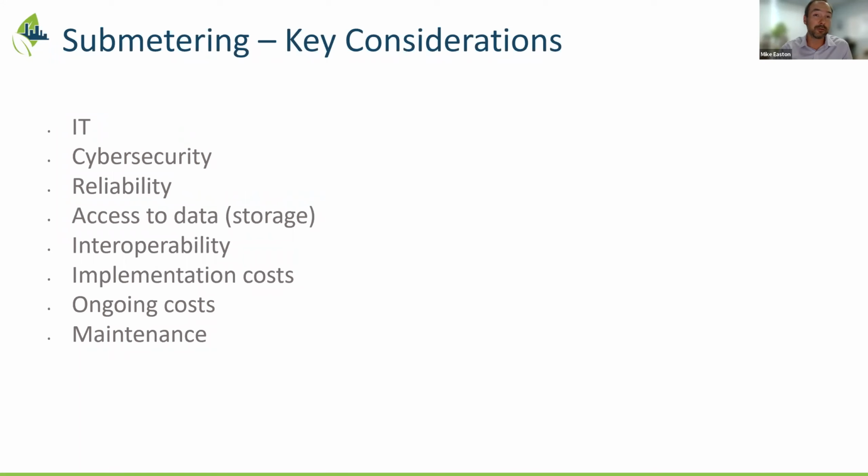You can have your data remotely collected by cellular, and you can have a direct Modbus integration into your BAS. You can do both if necessary. Once the data is collected online, you can really do whatever you want with it. You can utilize one platform to do all your reading and reporting, or you can API that data to a variety of different solutions. So if you have a benchmarking solution or an advanced analytics or fault detection solution, you can pass the data over there via API. Really, the data is yours and you can transfer it to whoever you need to.